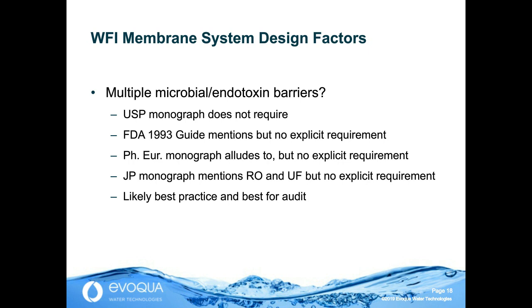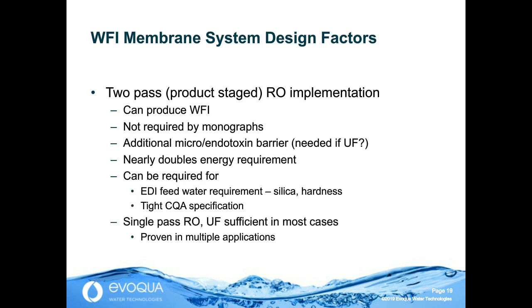Now, what about two-pass RO or product-staged RO, where the product from the first pass is purified again? Two-pass RO directly can produce WFI without ultrafiltration as a polisher and has in multiple systems. It's not required by the monographs. If you have a single pass of RO plus ultrafiltration, I don't think a second RO is needed. It can double the energy requirement for the energy to drive the second pass.